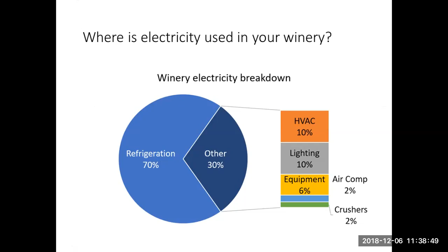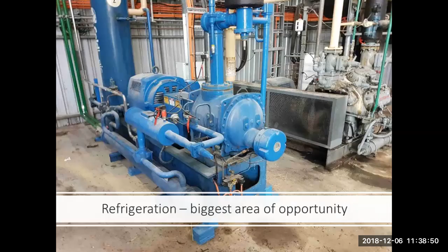So where is electricity used in a winery? As we said, it's mostly used in refrigeration systems. For wineries, refrigeration can account for up to about 70% of your energy use, and often this is what's causing those spikes in demand. Your fridge system ramps up as more activities occur, and this can increase the cost of your electricity. So what that tells us is that refrigeration is the biggest area of opportunity. This is where we should be focusing on implementing strategies and technologies because it's going to provide us the best results.